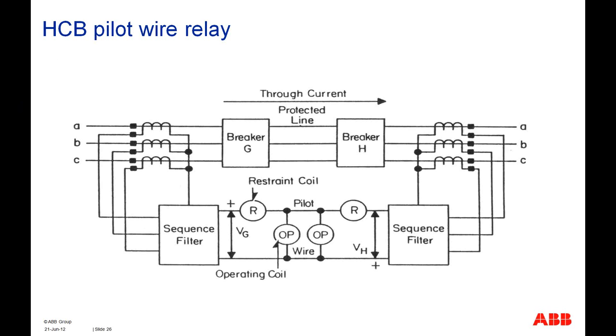So basically, this relay was working in this manner, that you have these 3 CTs with all these dot notations, and those 3 CTs were being fed to a sequence filter. And the job of this sequence filter was to produce an equivalent voltage, which is equivalent to the positive sequence, negative sequence, and zero sequence currents of this side of the line. And in a similar fashion, on the other end of the line, there was a sequence filter and a corresponding voltage, let's say, was created. Just a moment.